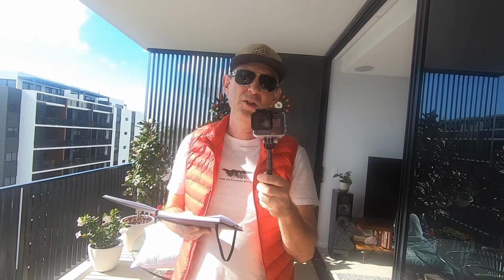So first there's a full test, which has 2 steps to it. One is called vent/gas. That takes about 5 minutes, and the instructions on how to set up the machine are on there, including the patient Y and whether it should be in manual or ventilator mode, whether you should have your APL open, closed, and this kind of stuff. So it's all on the machine, and then it will register 1, 2, 3, 4, 5, all the things it does. Then once that's complete, there's a circuit leak test.